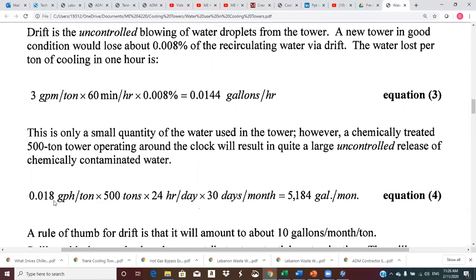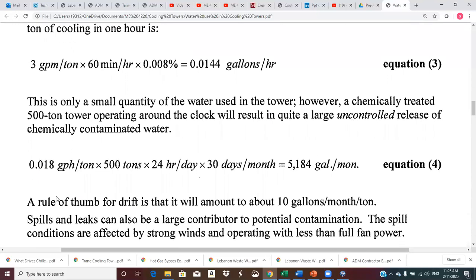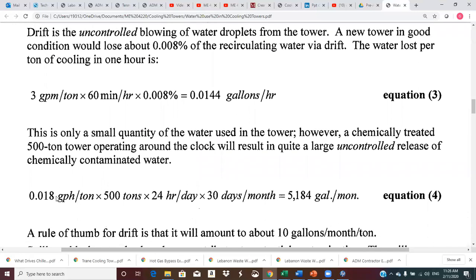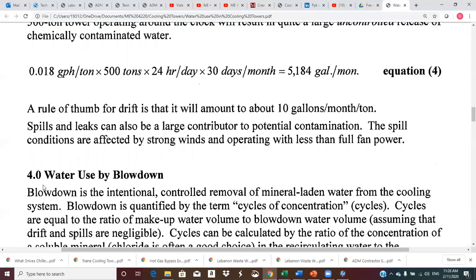But so in a month, if it operated full out at 500 tons, this chiller would evaporate, or I'm sorry, not evaporate, but this drift would be over 5,000 gallons per month. And then the evaporation is on top of that. So the rule of thumb for drift is that it will amount to 10 gallons per month per ton that operates for that entire month. So we had 500 tons for the entire month times 10 would be 5,000. A little bit better number might be 5,184, but it's pretty close. Spills and leaks can also contribute. Okay.